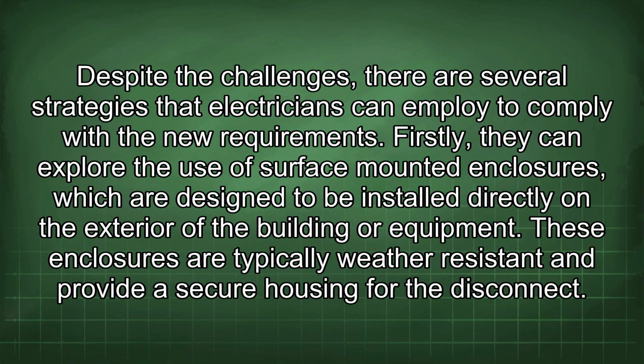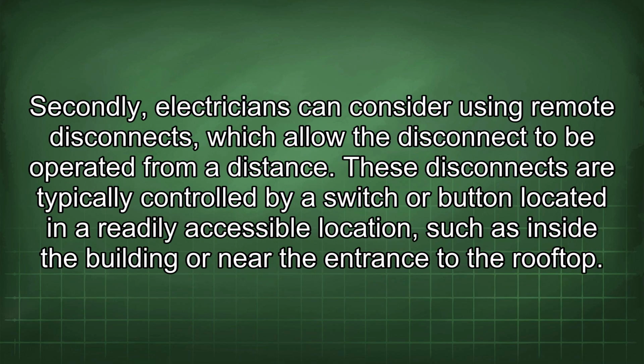Despite the challenges, there are several strategies that electricians can employ to comply with the new requirements. Firstly, they can explore the use of surface-mounted enclosures, which are designed to be installed directly on the exterior of the building or equipment. These enclosures are typically weather-resistant and provide a secure housing for the disconnect. Secondly, electricians can consider using remote disconnects, which allow the disconnect to be operated from a distance. These disconnects are typically controlled by a switch or button located in a readily accessible location, such as inside the building or near the entrance to the rooftop.